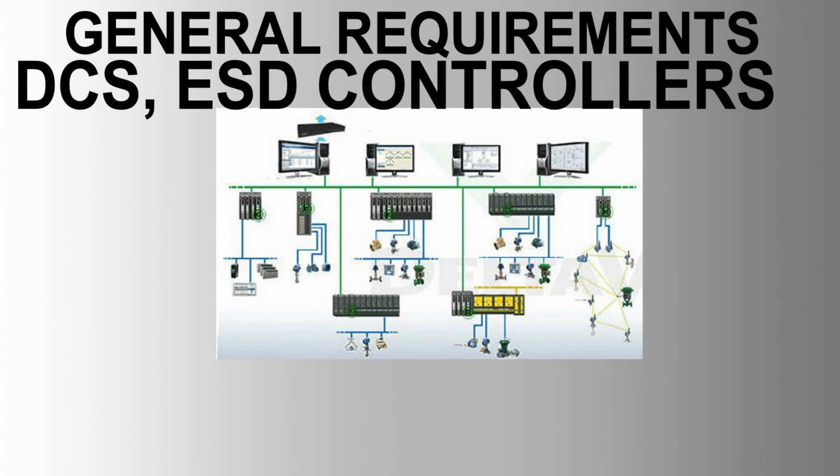4. Operator workstations. Specifications. High-resolution color graphics screen of at least 21-inch, capable of displaying mixed alphanumeric and graphic data. Sealed membrane keyboard with alarm annunciator LEDs. Trackball or mouse equipped with push buttons. Input-output mass storage units, floppy disk, DVD, CD-ROM drive. Ethernet Communication Interface Module. Workstations should support object-oriented distributed computing with client-server architecture, OPC client-server connectivity, and Explorer tree navigation with multi-window support.